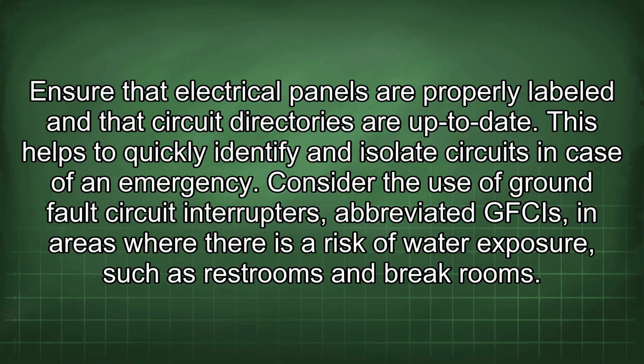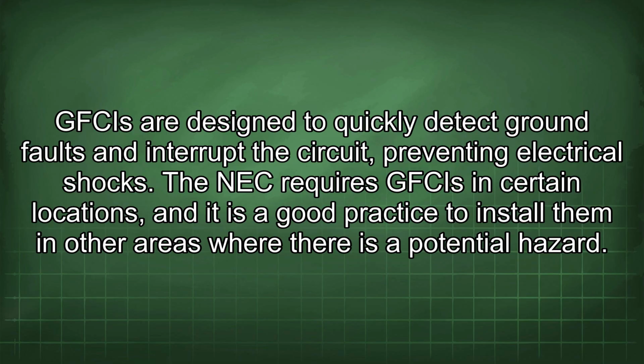Consider the use of ground fault circuit interrupters, abbreviated GFCIs, in areas where there is a risk of water exposure, such as restrooms and break rooms. GFCIs are designed to quickly detect ground faults and interrupt the circuit, preventing electrical shocks. The NEC requires GFCIs in certain locations, and it is a good practice to install them in other areas where there is a potential hazard.